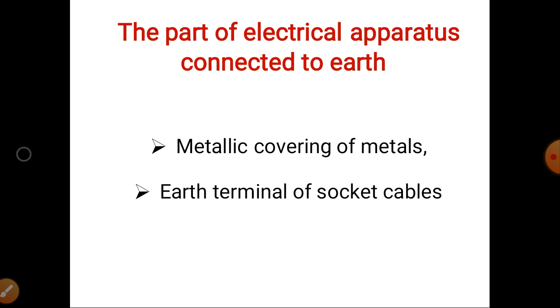The term grounding is used by some countries like USA and Canada, following NEC, CES, CEC, IEEE, UL and ANSI standards, so they call earthing as grounding. But the term earthing is used by some European countries and the UK, following IEC and IS standards. So depending on the standards followed by the country, they may call it grounding or earthing.